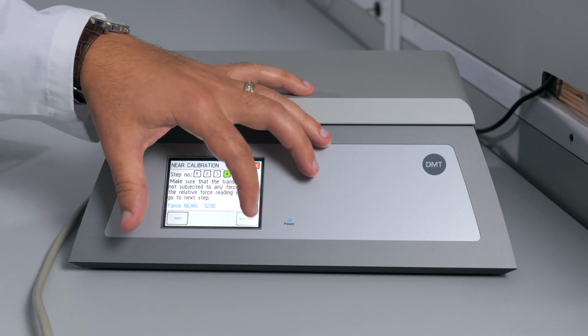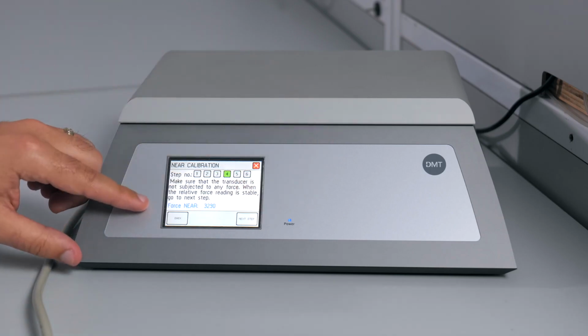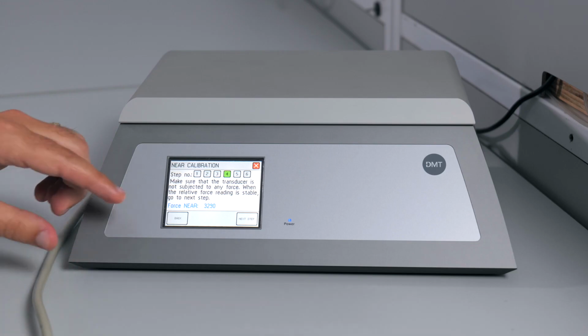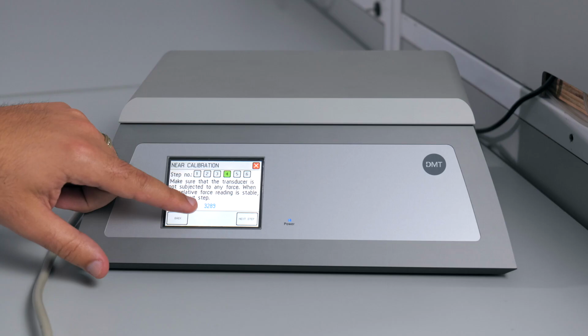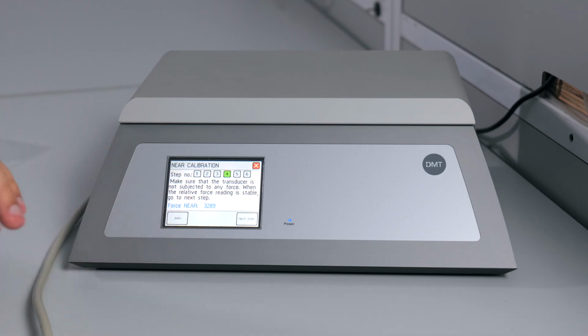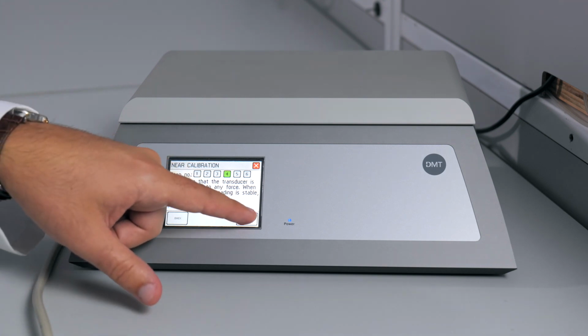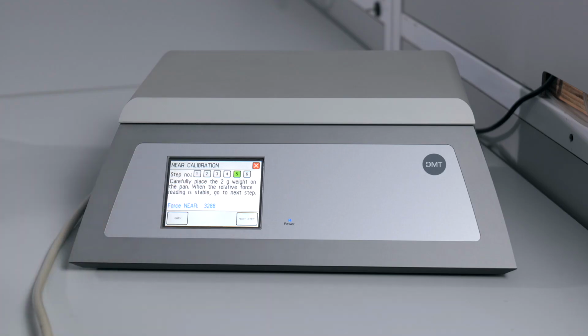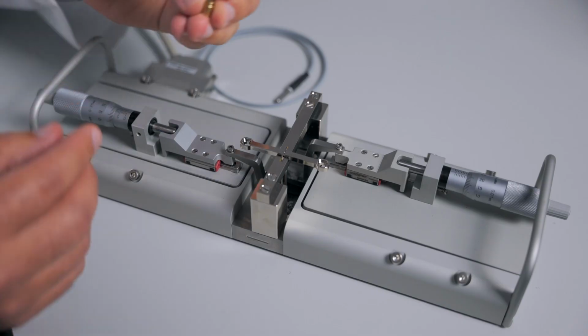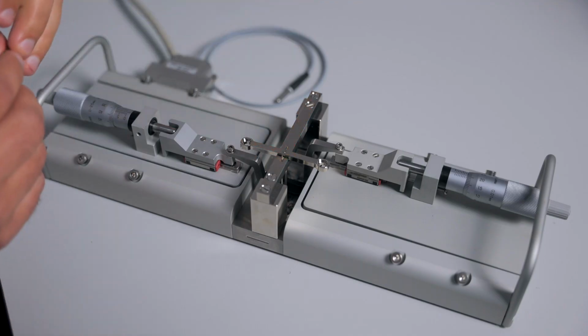Go to the next step, which asks you to make sure that the transducer reading is stable and not drifting in one direction. You will want to wait about 10 or 20 seconds to make sure it's not drifting. If it's going back and forth between 2 numbers, that's okay, but if it's drifting in one direction, it means that you might be touching the wire with the calibration setup. But after it seems relatively stable, you can go to the next step, which is step 5, which asks you to place the 2-gram weight on the T-balance.